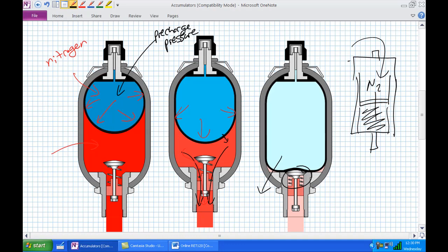There is a non-linearity because this is a gaseous system, and additionally there's some non-linearity for springs. With weight, it's always the same weight forcing down on it. Whereas with a spring and a gas charge, there is some nonlinearity. So it's not like you're going to get constant pressure to a certain point and slowly decreasing, you're going to get this nonlinear curve. The other thing that's weird about these, especially the gaseous ones, is charging it up super fast versus charging it up slow. I believe it's called adiabatic charging versus isothermal charging. There is a certain energy that is going into that gas. So you want to charge it up slowly, basically, so that it will store more energy over a longer period. Not only is there precharge pressure, there's a rate at which you charge these.